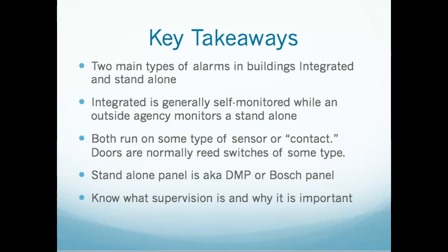You need to understand what supervision is and why it's important. Remember, it's a resistor in the line that sends in that last cry for help to tell you if somebody cuts the lines. If you don't have supervision in place, you won't know when a line's cut, and your alarm system is then worthless. So supervision has to be in place, extremely important, and you need to tell the installer to do it because they won't do it on their own.